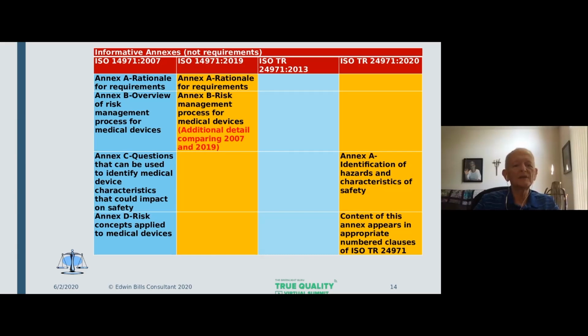So you'll notice 14971 2019 has Annex A, the rationale for requirements, which is a revised version of Annex A in 2007. Annex B in the 2019 version is a revised version of Annex B in the 2007 edition. And the really great value here is the additional detail comparing 2007 to 2019. And rather than my simplified table here, what you end up with is clause and subclause by subclause all the way through the two versions of a standard. So you can find things pretty easily, but it's a whole lot of detail.